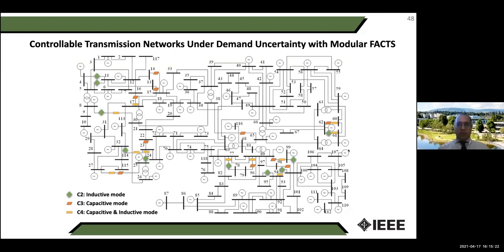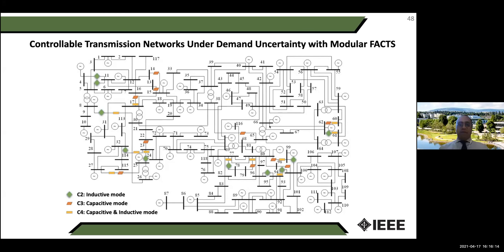Another optimization application involves FACTS devices in the system. These can change line characteristics — for example, the X value of a line. Increasing X reduces flow on that line and pushes it to parallel paths; reducing X increases flow on the line and absorbs flows from other lines. This helps manage congestion in the transmission network, avoiding installation of new transmission lines and utilizing existing assets more efficiently.